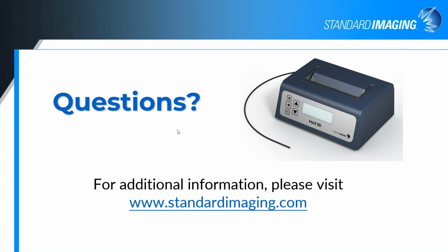A question about the most accurate, least measurable dose. That's a good question. Actually, I don't have that number offhand, how low a dose you can measure. I will say that the W2 was designed so that when you scan with it and you get to the edges of the penumbra, to the out of field tails, we wanted to make sure we had enough signal to be able to measure those tails accurately.